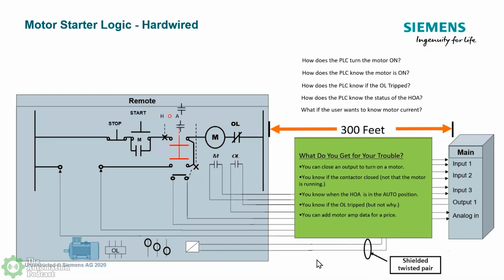So what do you get for all that? Really, you don't get much. You get a status that that contactor's pulled in, and that's about it. But let's say we're doing a conveyor belt. If somebody's sitting in a room with no windows, they can't see the facility other than what they see at their panes of glass or their monitors, what do they use for that indication that everything's running just fine?